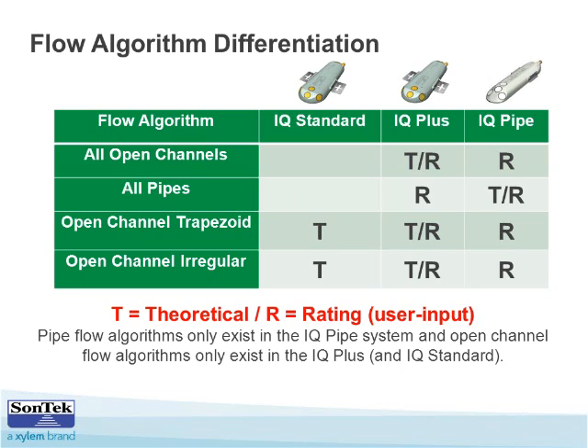The IQ Standard is the most basic model. It will allow you to measure flow in any open channel situation, irregular or trapezoidal, but it will only output using SonTek's proprietary flow algorithms. If you don't do complex modeling or develop ratings, you might not need extra processing capability—all you might need is an IQ Standard. But if you need open channel flow with the ability to do more post-processing, to see more parameters, and to actually get that velocity profile information in your hands, you'll need an IQ Plus model for open channels.